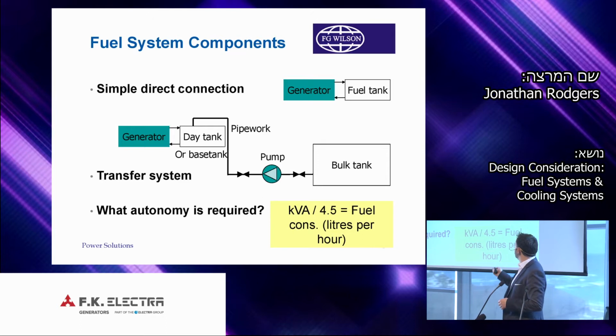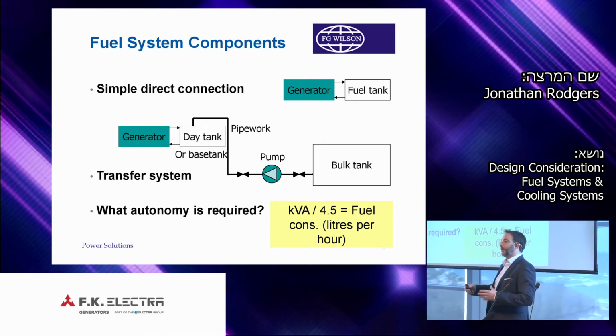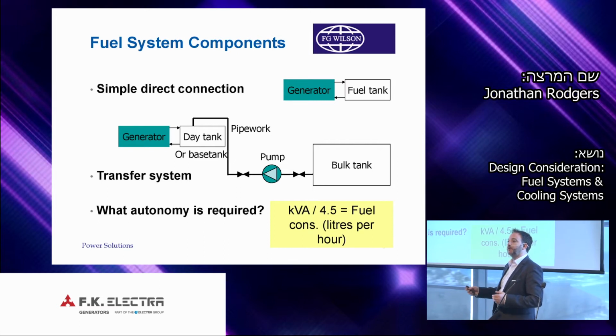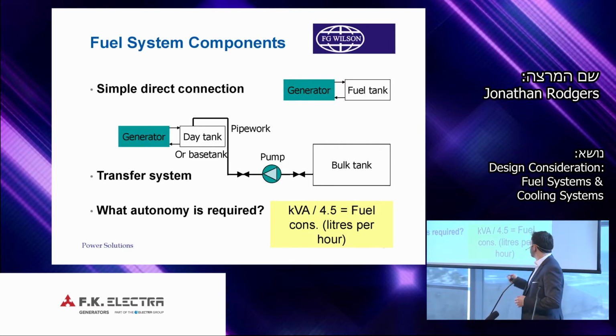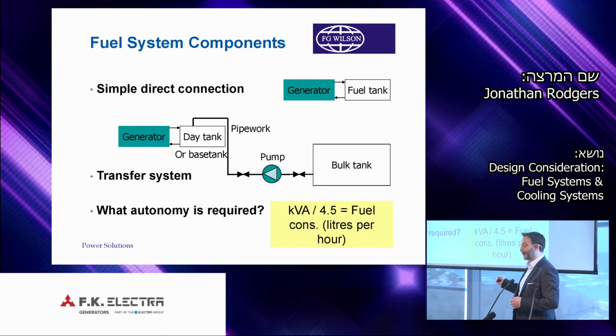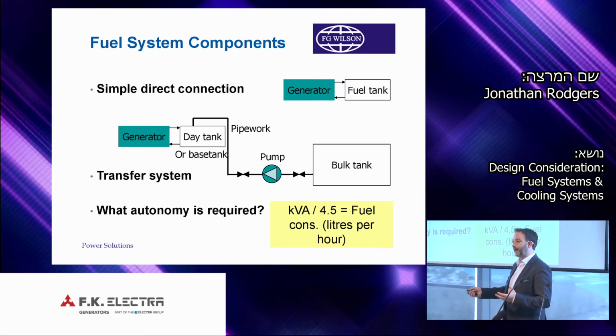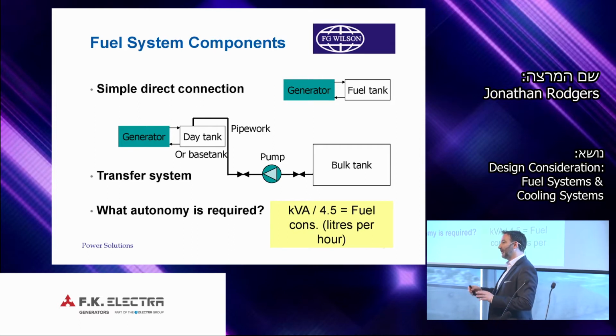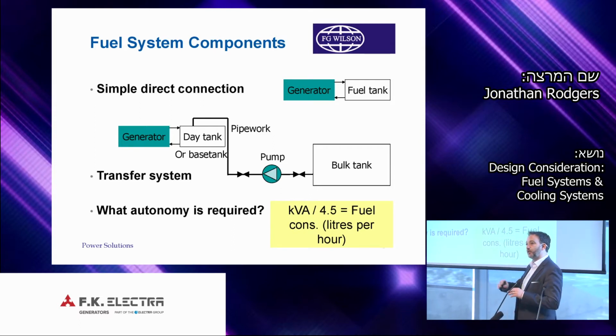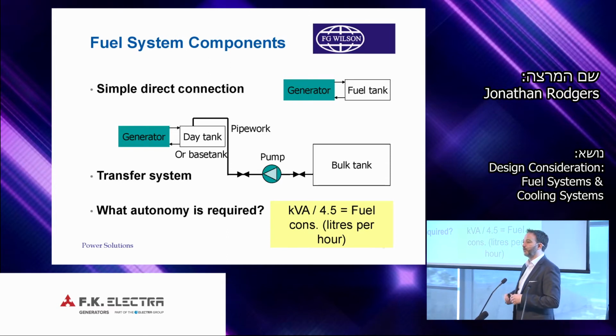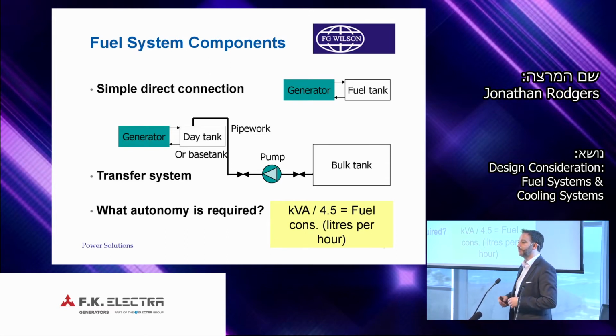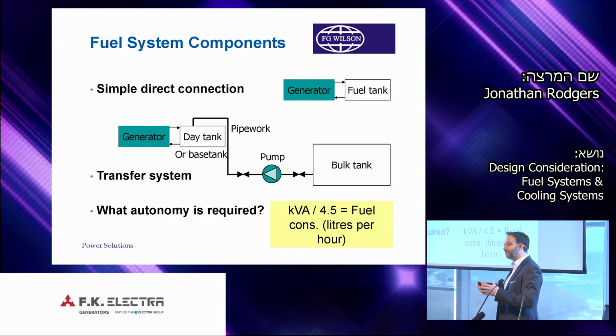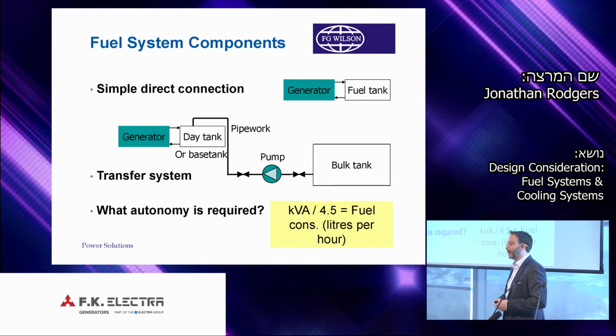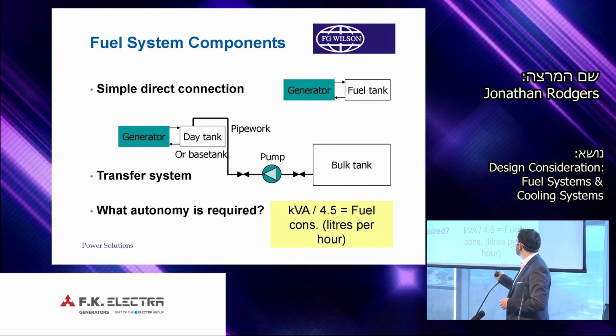A quick note when we're sizing the tanks is the autonomy, or how many hours of operation do we need. And from a basic design, if we take the kVA of the generator and divide by 4.5, that gives an approximate fuel consumption figure for most of the range of engines. So it's a quick design sizing for tank volume if we're looking at an installation.